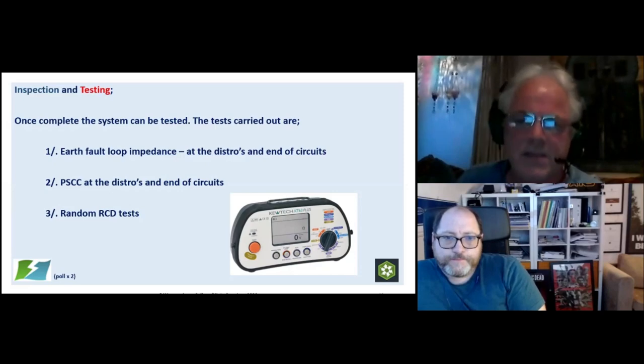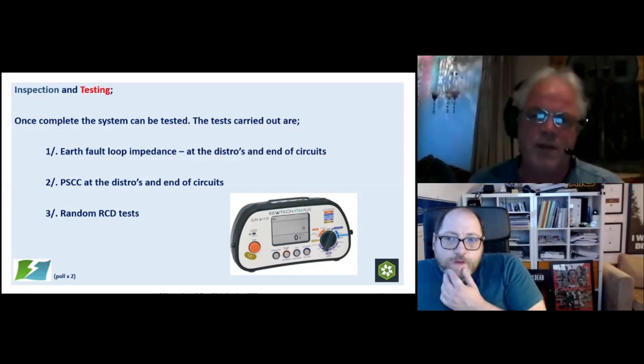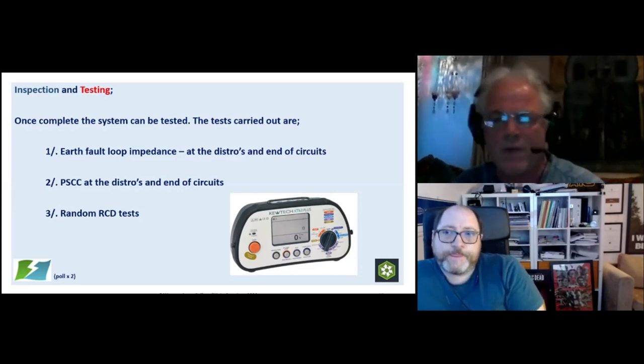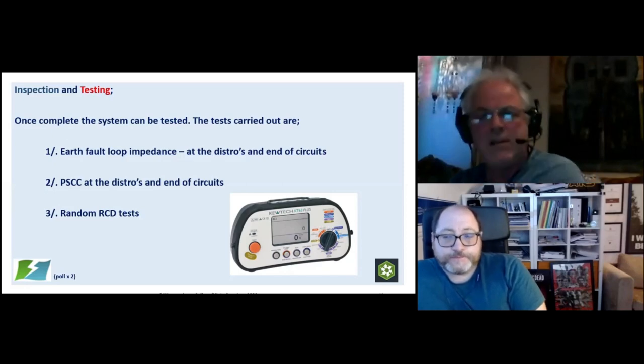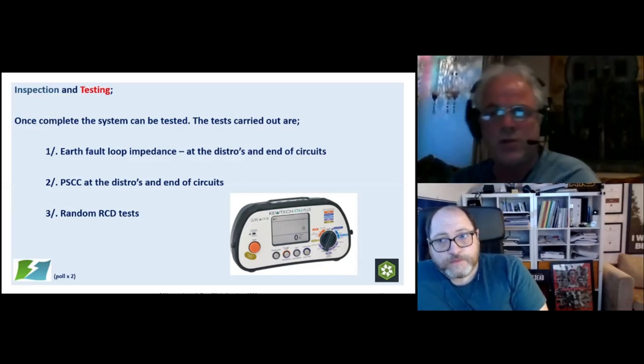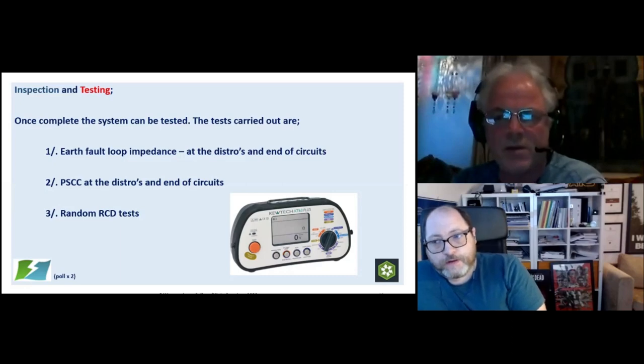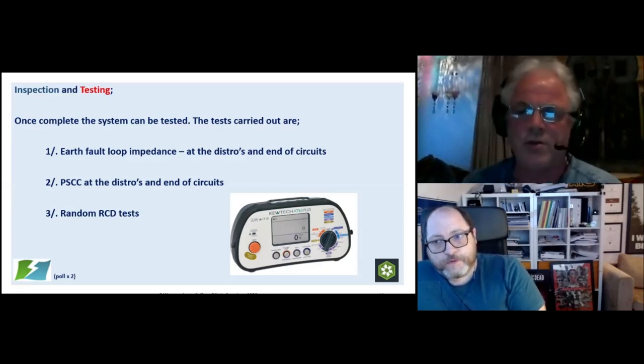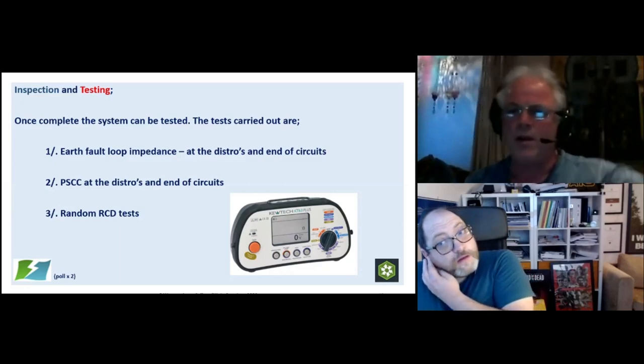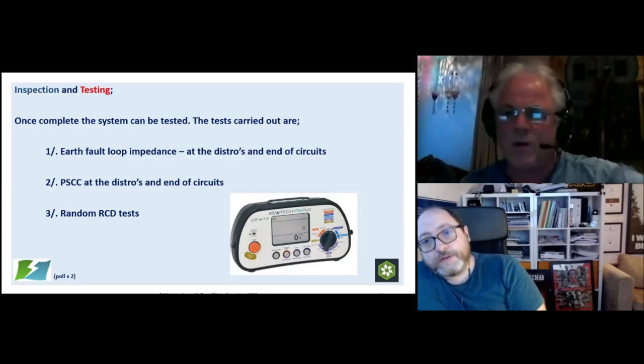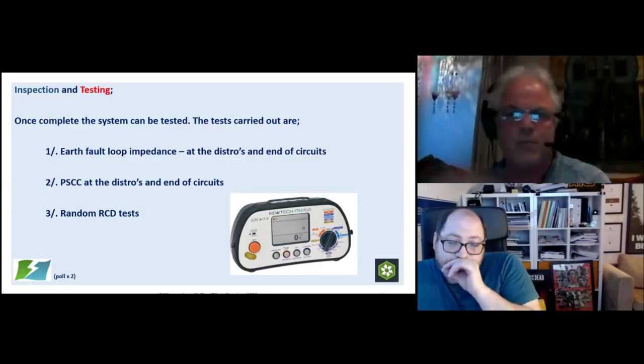So this is a very important test that we have to do on temporary. We look at doing fault current tests, short circuit, at the end of the circuits. And this was new to me when I first got into doing temporary. You know, being an installation electrician, I'm used to doing fault current at the intake and at the main distro. And once you get to a certain level, you don't bother anymore.